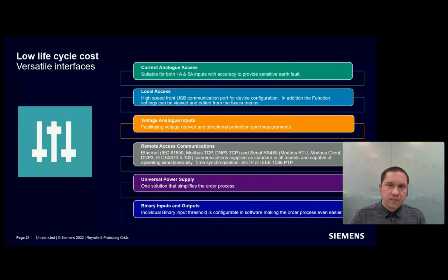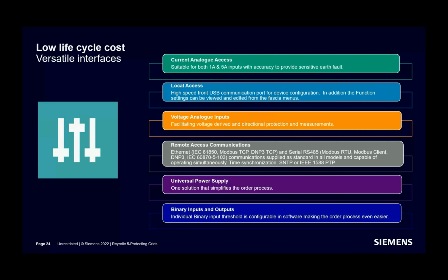Now, I would like to summarize the versatility Reyrolle 5 devices provide as standard. As I said before, this is a summary after all. The CT inputs are suitable for connection to both 1 amp and 5 amp current transformer secondary windings, while the user is able to use the high-speed USB communication port for device configuration. The fascia allows the user to view and edit all the function settings inside the relay without the need for a PC and configuration software. And all 7SR5 devices have dual-link Ethernet communication port as standard. The user needs to choose only the interface type as either RJ45 electrical or optical, and this provides all IEC 61850, Modbus TCP and DNP3 TCP as standard at the same time.